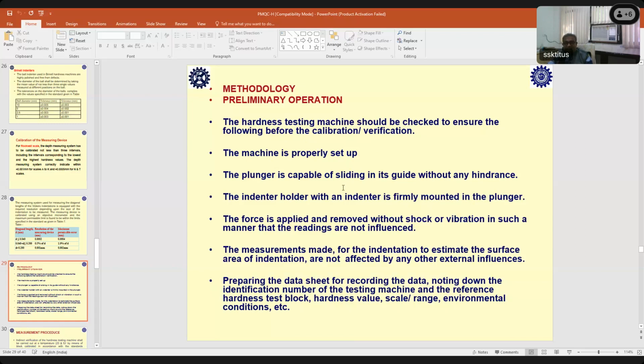And the plunger is capable of sliding in the guide without any hindrance. So this is again a very, very important thing. Normally we engage and disengage the plunger in the hardness machine to make the indentation. So there shouldn't be any other frictional component hindering the movement of the indenter. If that is happening, then the applied force will not be the same, and we may not be able to make out all those things. We might have calibrated the machine for force, but when you are making the measurement, it is better to check whether the indenter is sliding freely without any frictional force acting on it. Okay, so that is why it is written.